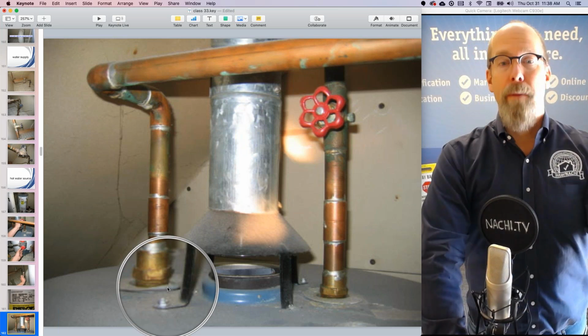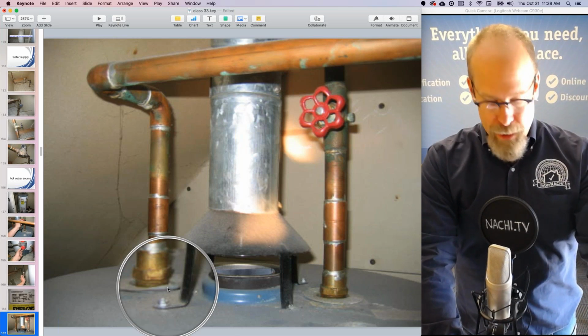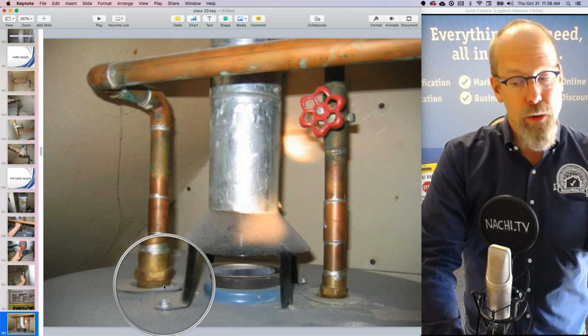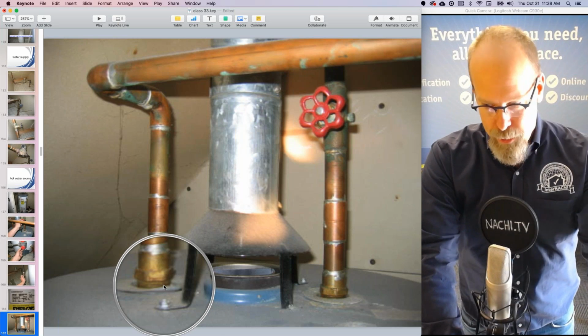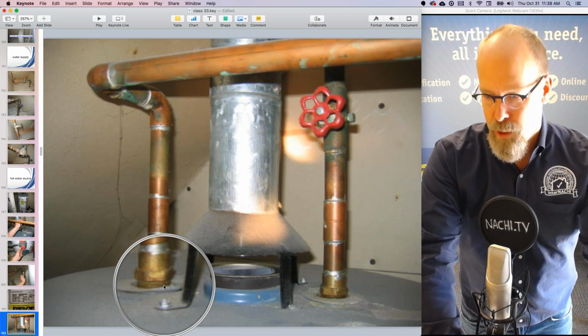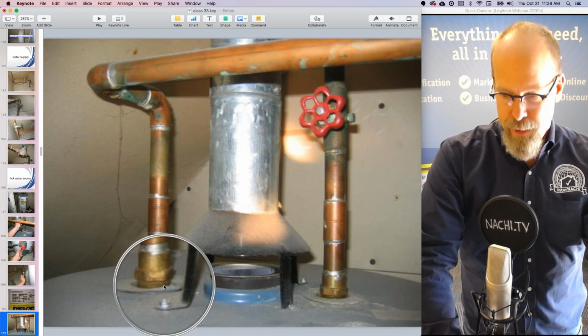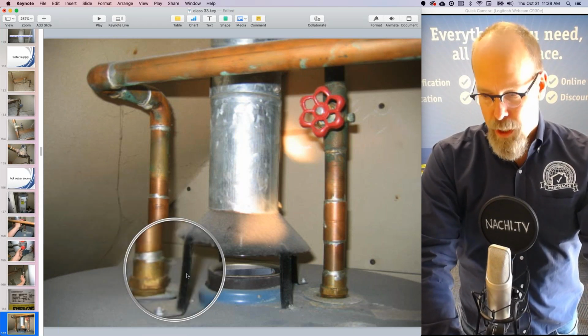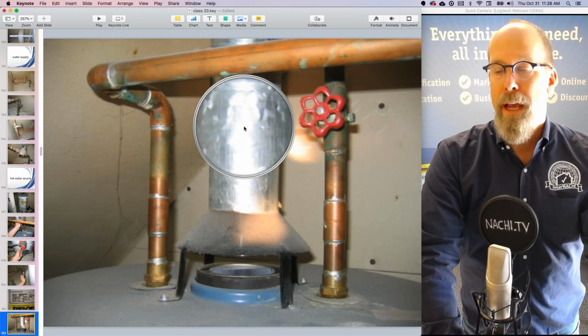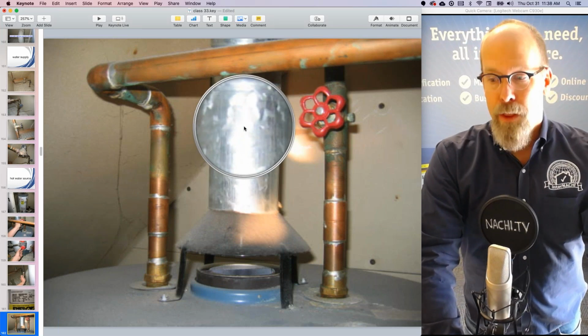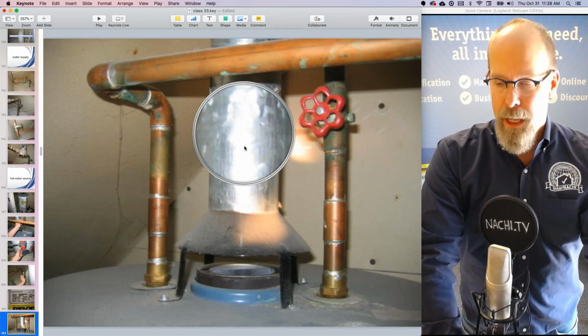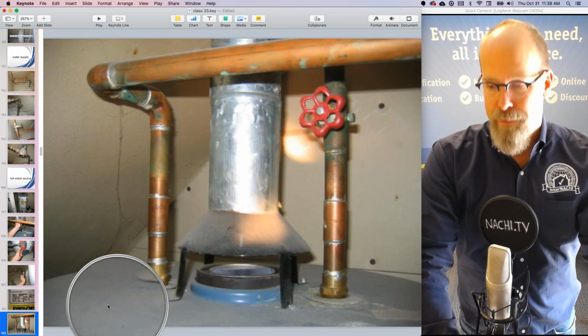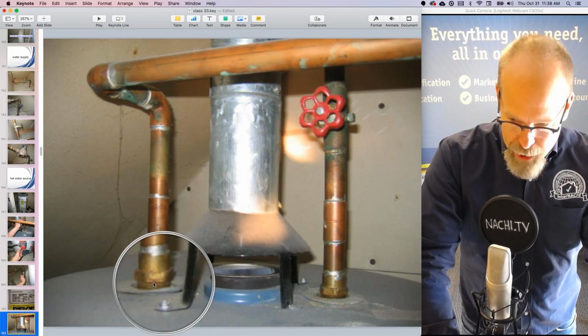There should be a carbon monoxide detector installed as well, according to local code or national code or best practices. Whenever there's a natural vent, natural draft, that means air from the room is going up into this flue pipe, and there's no fan. There's a possibility of it backdrafting, and it's hot flue gases.